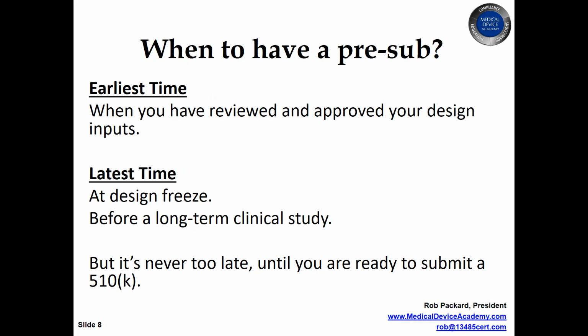And so my recommendation for the timing of when a pre-sub should be is sometime between when you approve your design inputs and when you approve your design outputs. During that development cycle where it's probably an iterative process and you're making changes rapidly to the device design and maybe trying them out either in cadaver labs or in animal studies or on bench tests, and you're seeing what works and what doesn't work, this is a great time to be having discussions with the FDA about what testing will be required so you can maybe do some preliminary screening against the different tests to see what is going to have trouble passing and what is going to be pretty easy. Then you can quote and plan that testing.